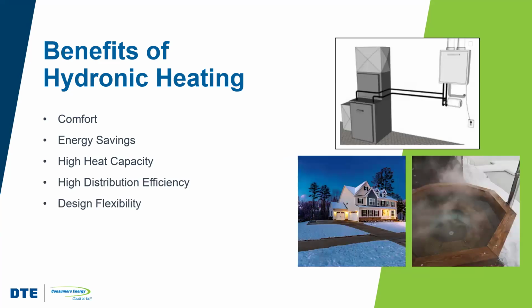Hydronic systems may also be a little bit more flexible than forced air systems because they can serve multiple loads, right? So they can serve pool heating and snow melt systems with the same equipment. This reduces the required installation cost because now you don't need multiple heating sources. You don't need a boiler for space heating, a separate boiler for snow melt, a separate boiler or a separate pool heater, right? That can all just be one piece of equipment.